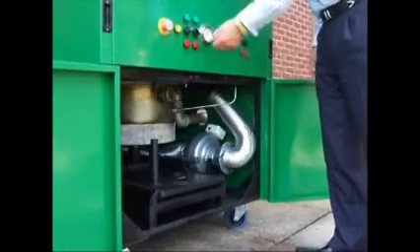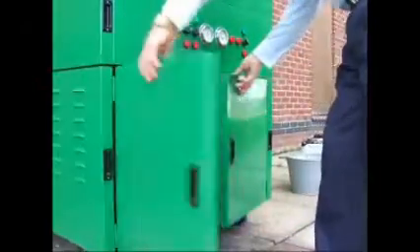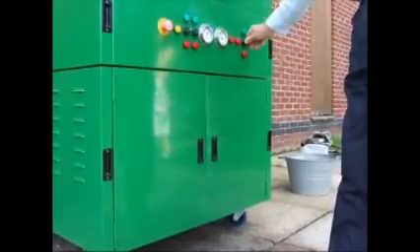Check the boiler is alight through the sight glass. Switch on the burner fan, switch on the oil feed pump, close the doors and turn on the water circulating pump.